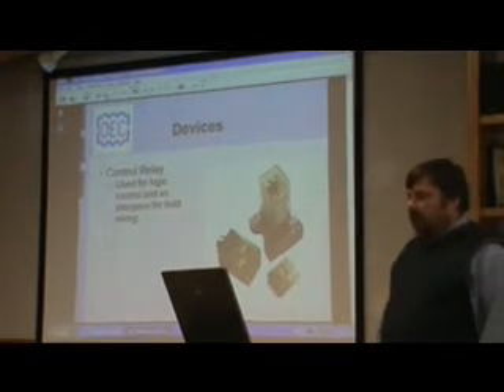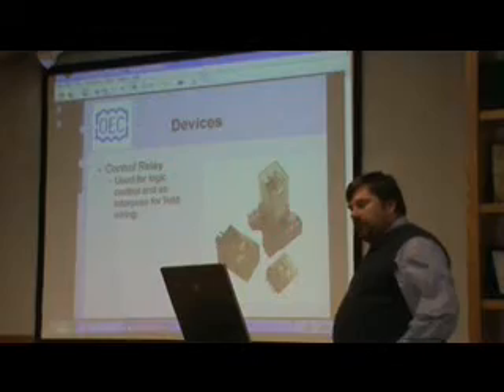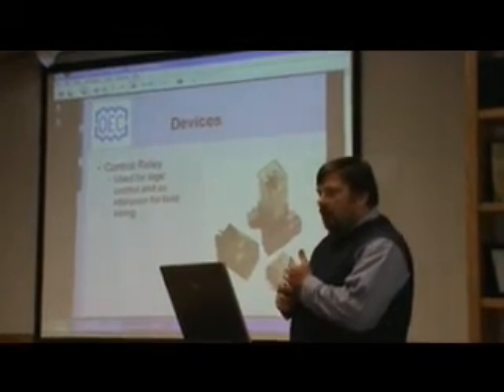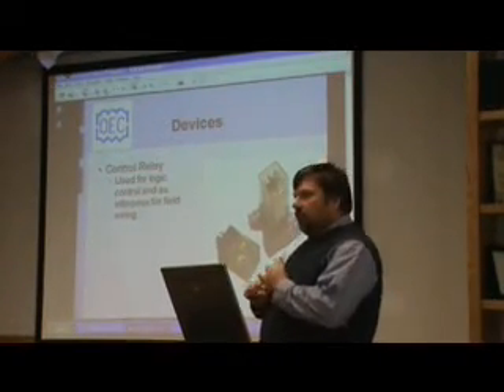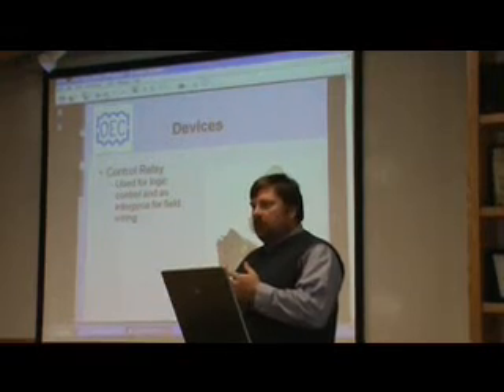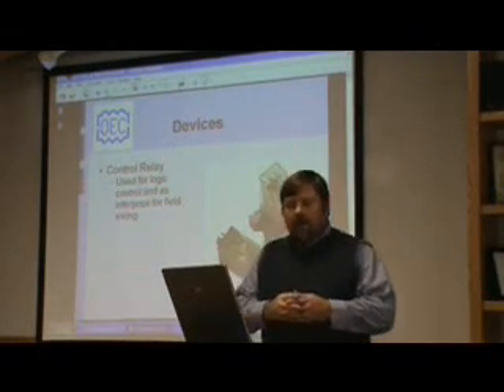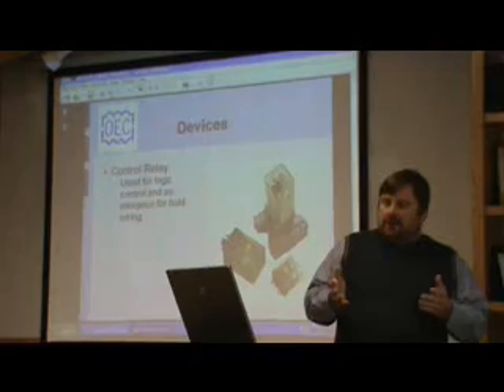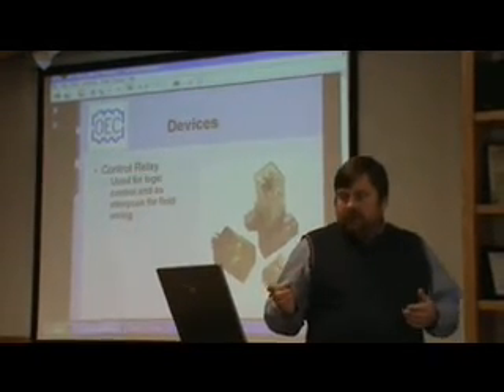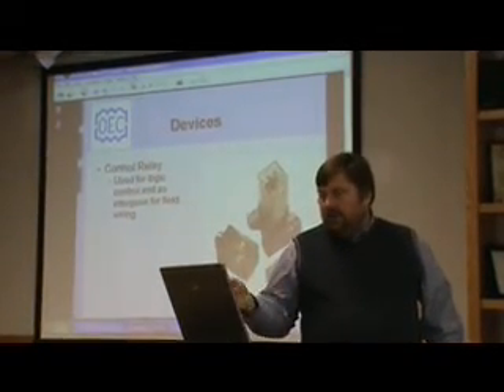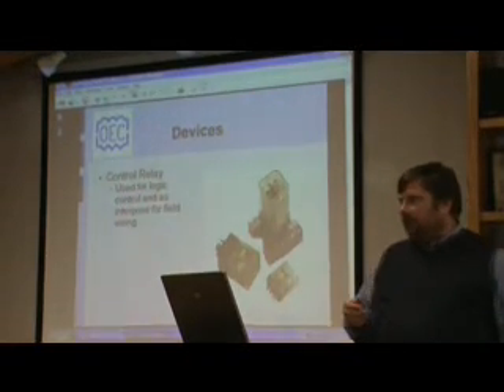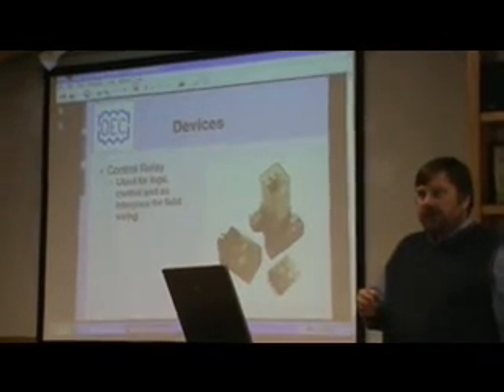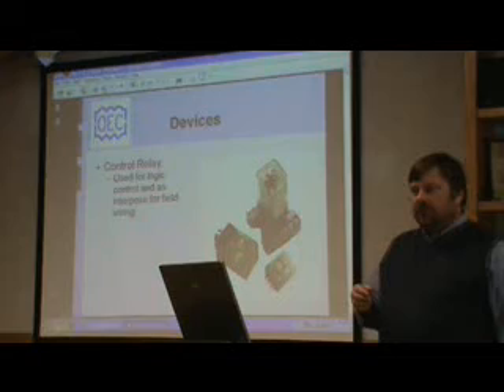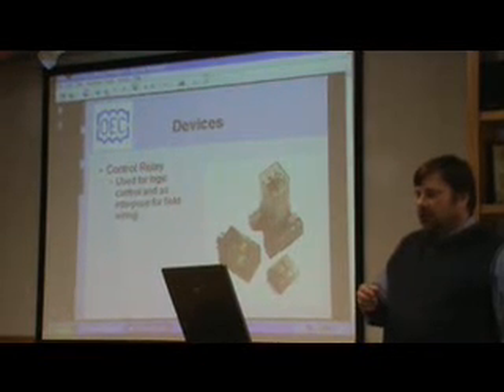You'll see control relays used in panels for a couple different purposes. To latch circuits on, to give indications for remote, run signals or alarm signals and things like that. So it's just little ice cube relays. I'm pretty sure everybody's seen them. We use IDEC in ours. We've used them for about 35 years and have had, I think, one relay go bad over the 35 years that we've heard of. So they're a pretty durable product.